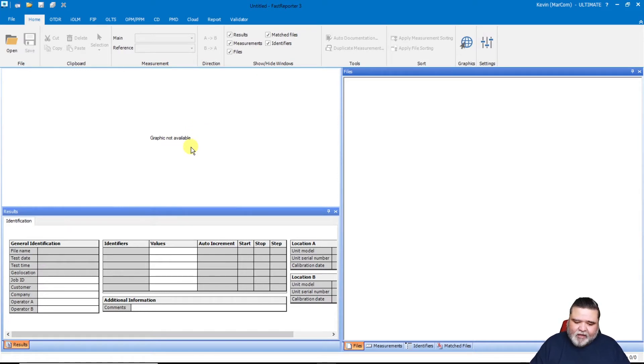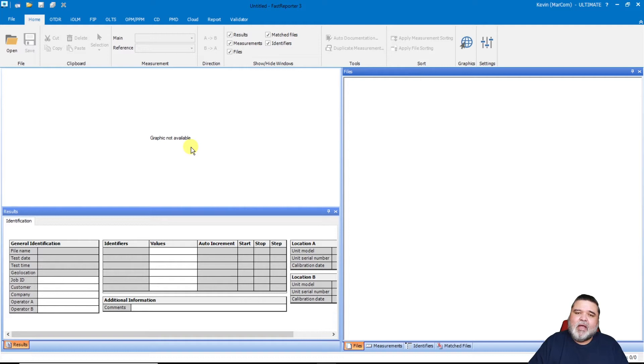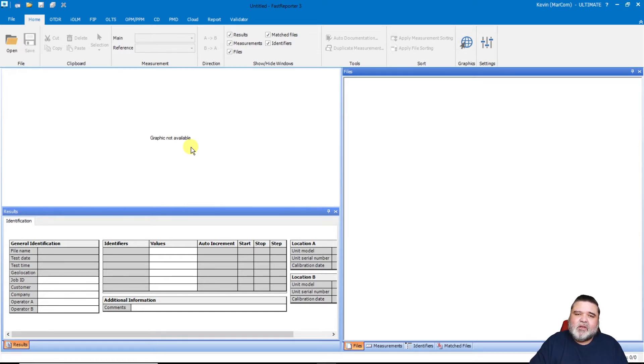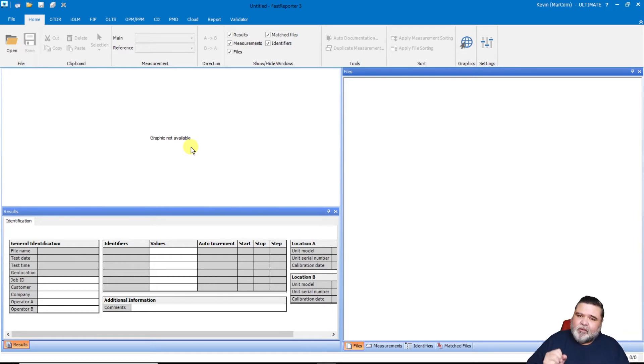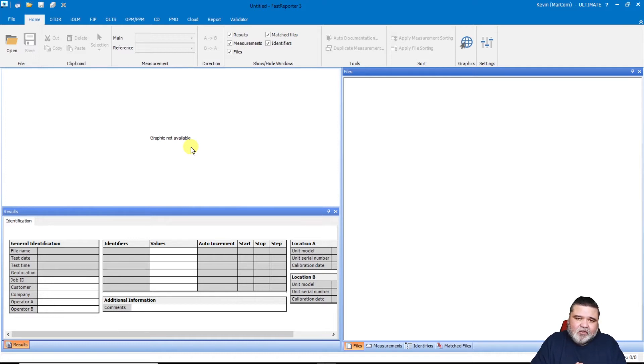The first thing I want to do when I start up Fast Reporter 3 is create a project file. A project file is essentially the thresholds, settings, and parameters you want to use to define the reports and analysis — it's almost like jobs. If I have different thresholds for different customers or organizations, I would create individual projects for each. So if I'm doing a job for Acme Construction or some generic power company, I would create individual project files for those customers.